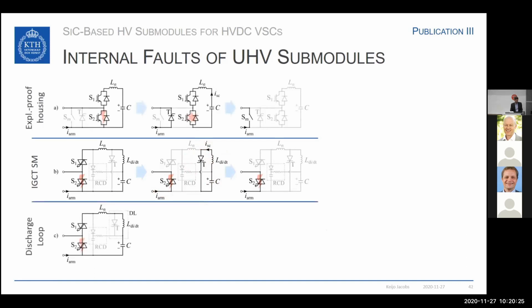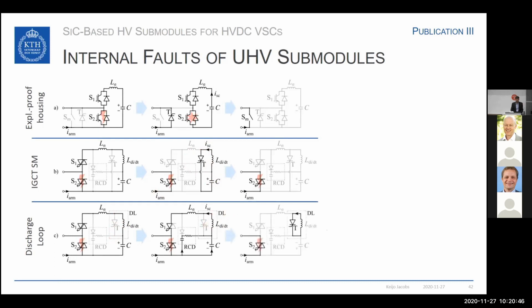Therefore, in publication 3, we proposed the use of a discharge loop. In this case, we arranged the bypass capacitor only across the inductor. So if a fault occurs, first the capacitor will discharge through the half bridge, as seen here. The discharge is limited by the di/dt reactor of the cell. As soon as the whole energy is stored in the di/dt reactor, which usually happens after about a quarter of the oscillation period, we can fire the bypass thyristor and discharge the energy through this dedicated discharge loop.